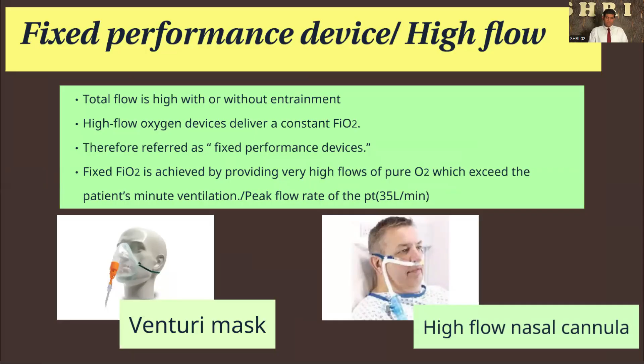So the Venturi phenomenon, or Bernoulli effect, is where we are using the airflow through a narrowed opening that decreases pressure, a jet that will entrap the ambient air. That is the key phenomenon we are using. Even if you connect 15 liters of oxygen to the green color funnel, it takes a high amount of atmospheric air, and that gives 60% FiO2. So always we are giving the fixed performance, the fixed amount of FiO2, because of this Venturi effect.